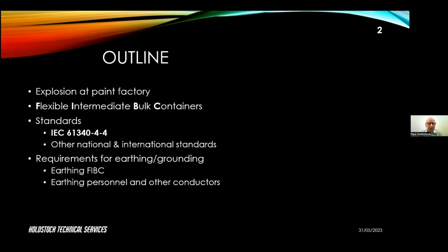So I will explain a little bit about this explosion, but then concentrate on the main standard, which is an IEC standard 61340-4-4. I'll also mention some other national and international standards. I'm not going to go into too many details about those specific standards, because essentially they contain the same guidelines and the same important information that's contained in the IEC 61340-4-4. And then in terms of the actual detail, I'll look at the requirements for earthing or grounding, both of the FIBC themselves, but also earthing personnel and other conductors.